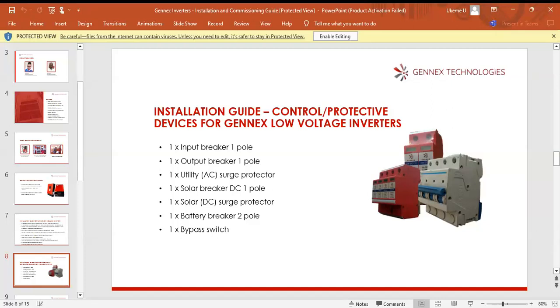You also need a protector for PV, which is a DC surge protector. Then you have one solar breaker, a DC one pole. Then you have two pole, because it's not so easy to get a 125 amp, 250 amp breaker for a 5 kVA inverter. So you can loop one two pole 125 amp breaker to achieve your 250 perfectly. Then you need a bypass switch to make the system transfer from direct to inverter smooth. Your client can do that. If there's any issue, he can easily flip to direct, which is bypassing the inverter until the problem is sorted out.